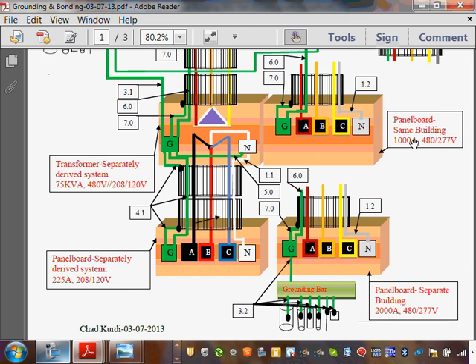That's a new service conductor. You bond the neutral at the barn. You go to the house, you bond the neutral at the house. You're taking service entrance conductor. That's one way of doing it. Now you put your overcurrent protection device right at the isolating device to the side.